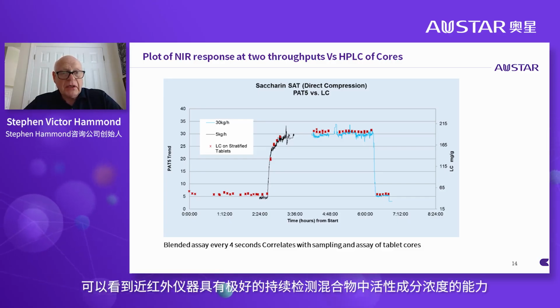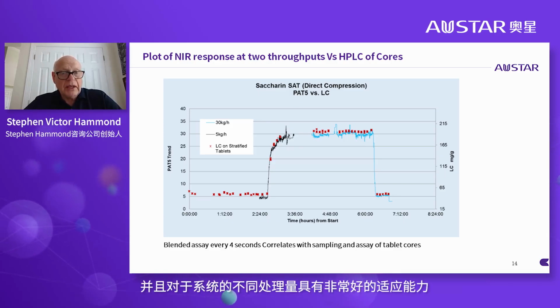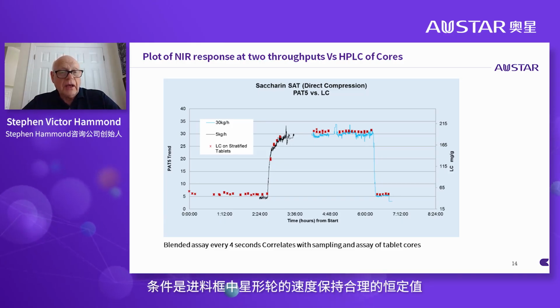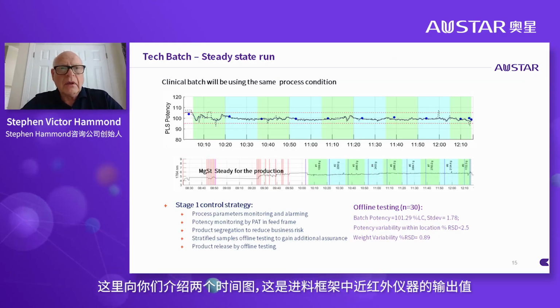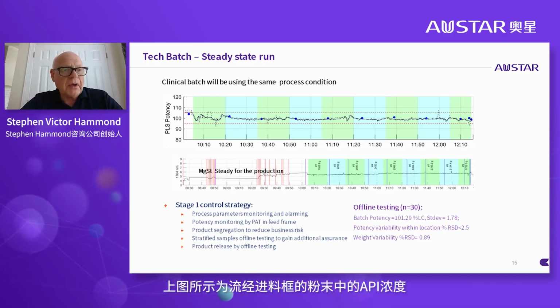So you can see the ability of the near-infrared to constantly monitor the concentration of the active ingredient in the blend is extremely good and is very tolerant of different throughputs through the system, provided the speed of the spider wheel in the feed frame is kept reasonably constant. So here I want to show you two time plots, and these are the output of the near infrared in the feed frame. The top plot is showing you the concentration of the API in the powder as it's passing through the feed frame.